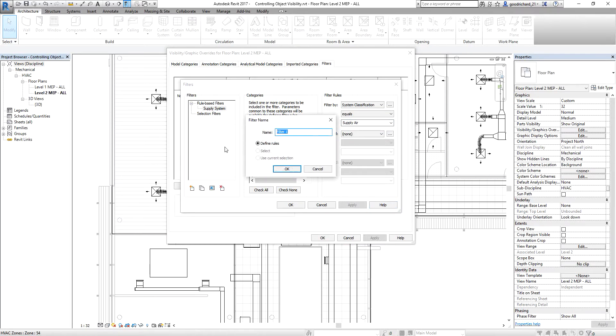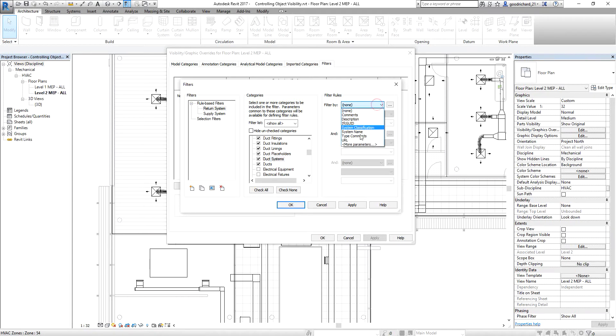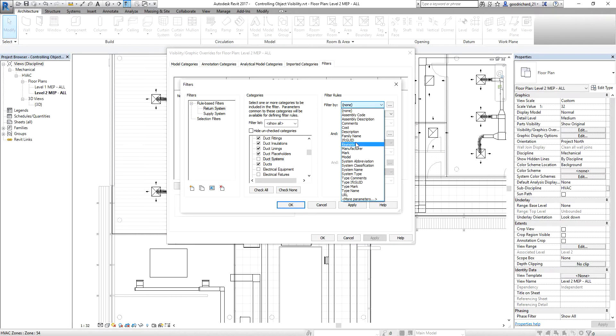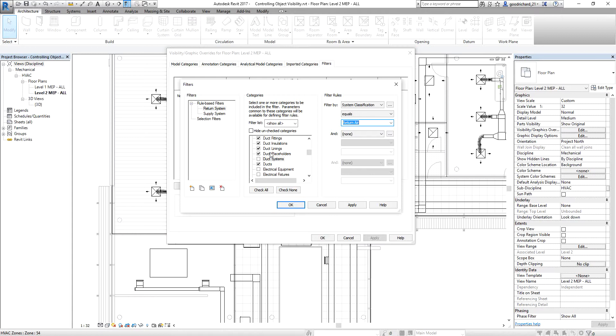After that I create a new one — this is my return system. Same procedure: I select the duct, accessories, linings, placeholders, and ducts. The reason I'm not selecting duct systems is that if I click that, the filter rules available will be very limited. So I'll just uncheck it. I select system classification equal to return air. So this return system filter will include these categories where system classification equals return air.